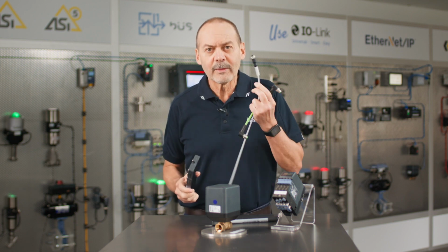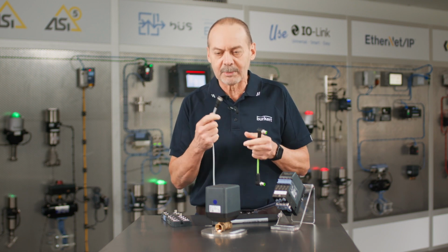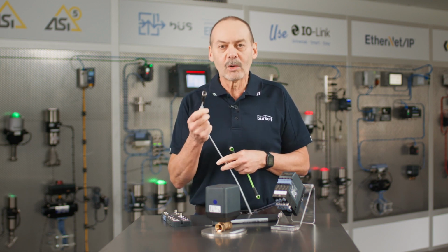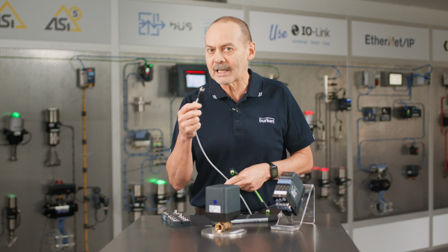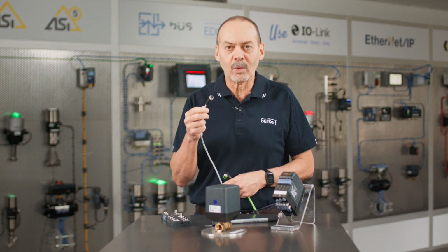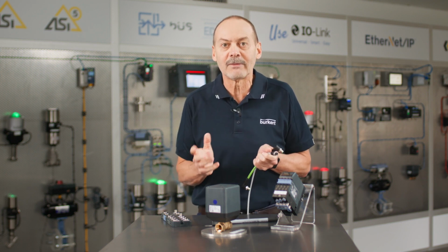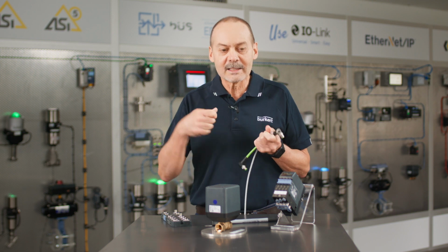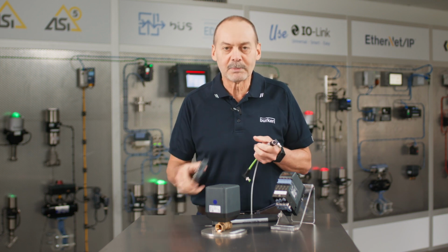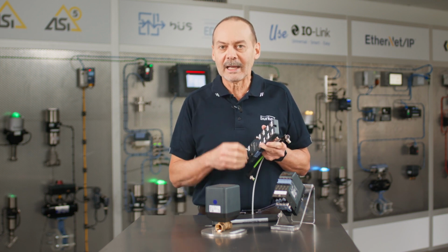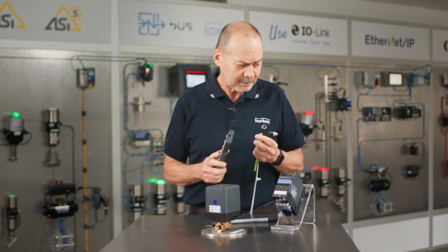Secondly, try wherever possible to use molded cables. These molded cables are made in very, very precise methods, and they all come pre-tested so that you know when you connect these, they are meeting the IP67 or 69K and that they do work. Sometimes if we use field wireables, and I'm not saying that we can't use them, but sometimes you have to, you do find that there's manual intervention, there's chances for cable termination problems, etc., and air gaps in there that can fill up with water and things like that. So wherever you can, use the molded cables.